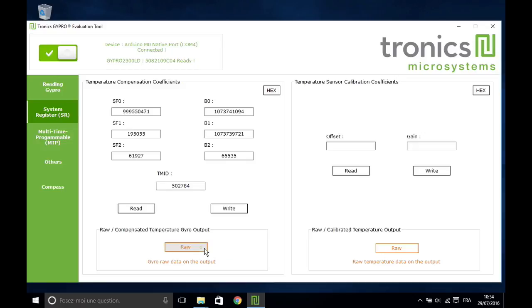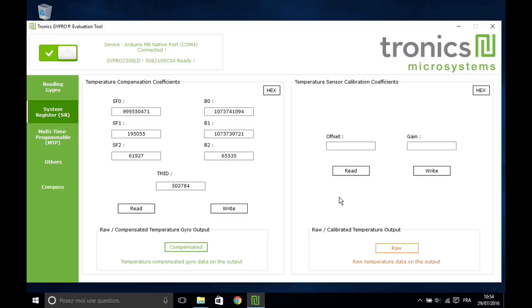The toggle at the bottom of the window enables switching from raw data to compensated data output. Decimal values can be converted to hexadecimal. The right box is useful for the calibration of the temperature sensor.